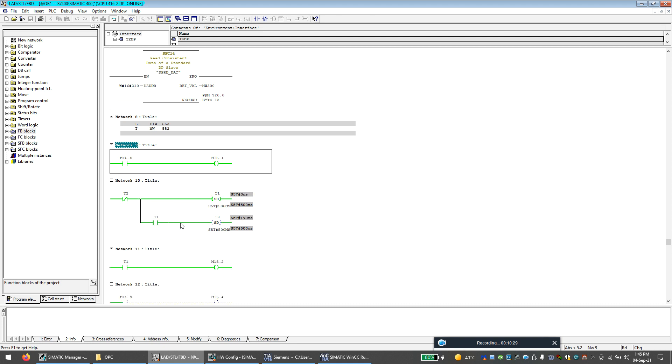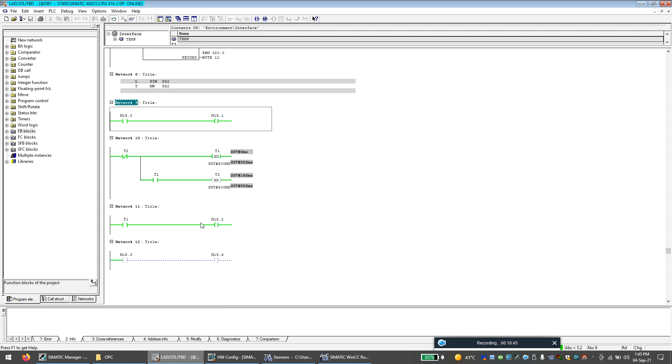So it is always good to have a continuous running script in the SCADA system. What we can do is we can make an on-off pulse like this. This is giving a pulse every 500 milliseconds. So I can use this bit to run a continuous script in the WinCC SCADA system.